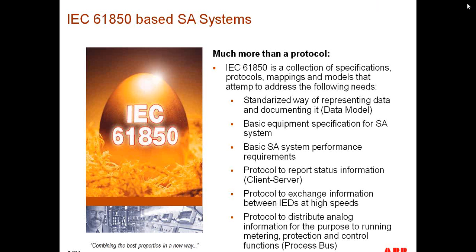When looking at IEC 61850, it's very important to take into consideration, and this is a very common question that we always receive, that it's really hard to define what 61850 is. But one of the first starters is that it's not a communications protocol. It's really a combination of points, a combination of needs that the industry as a whole had with its introduction. And one of them is the need for a standardized way to represent data and document it.